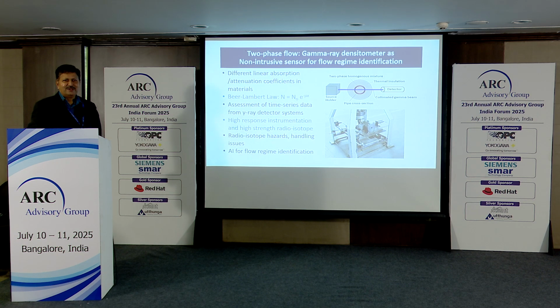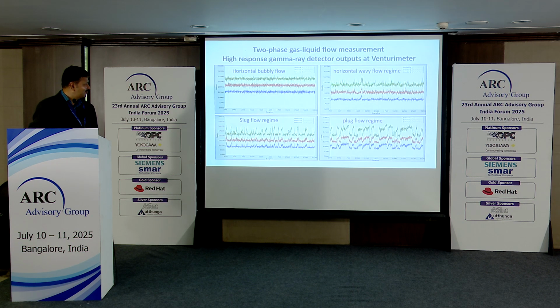So the only drawback is, as I said, the radioisotope handling, and it is very difficult to get an approval if we want to go for multi-phase meters with such high strength of radioisotopes. Especially, you know that in the petroleum industry we see multi-phase flow meters which may have a response time like 1 minute, 2 minutes, and we go for a much lower source strength.